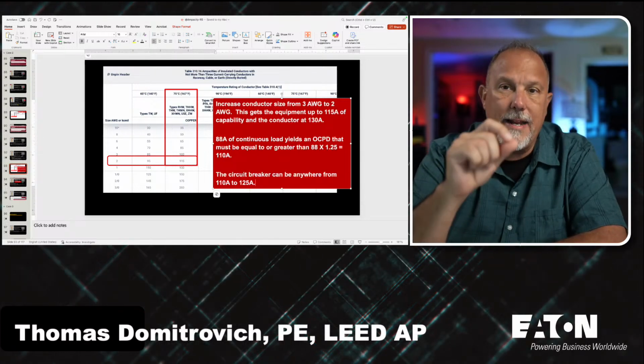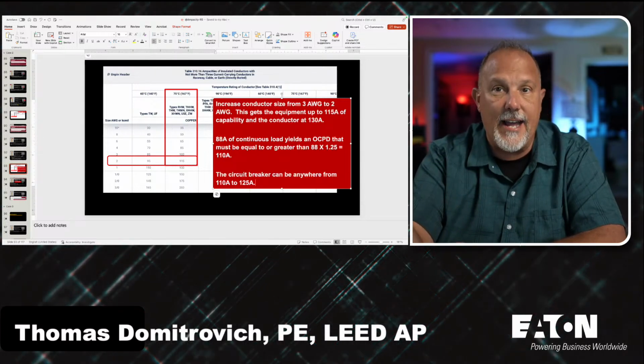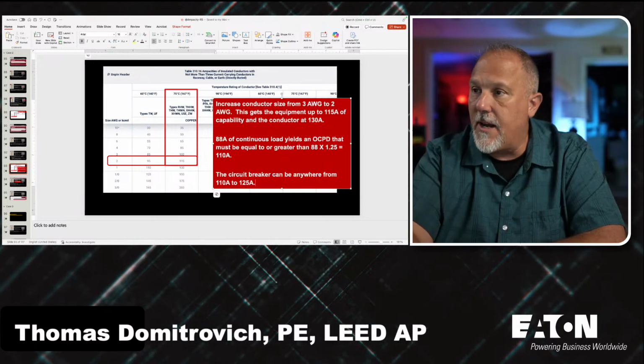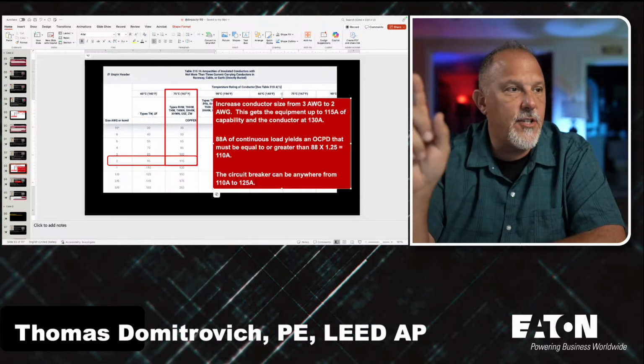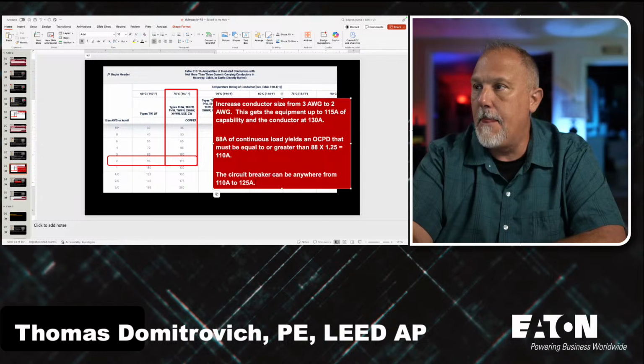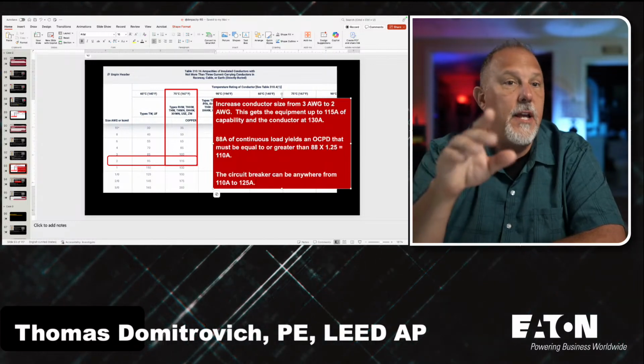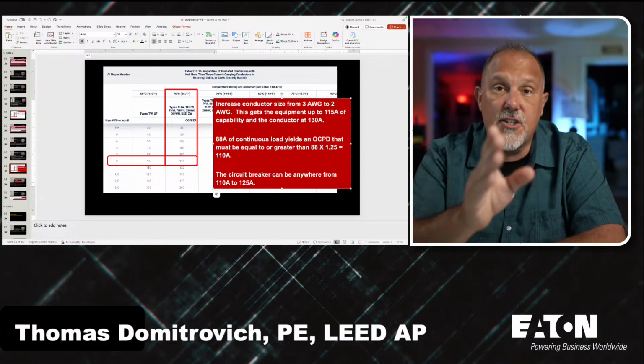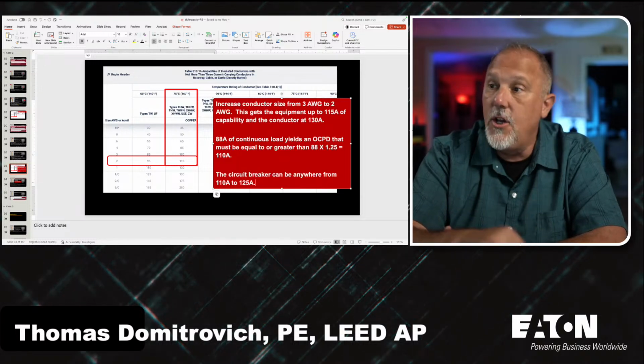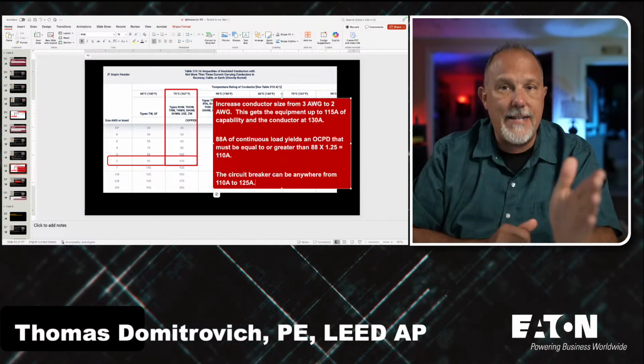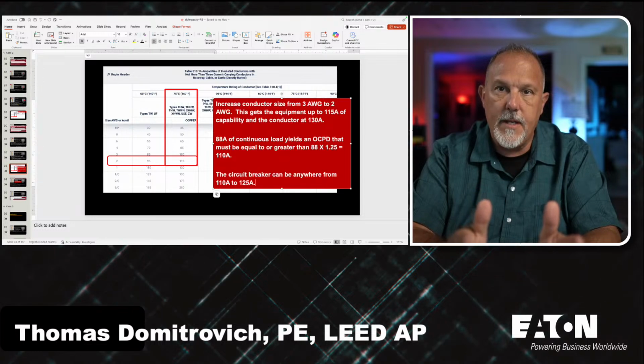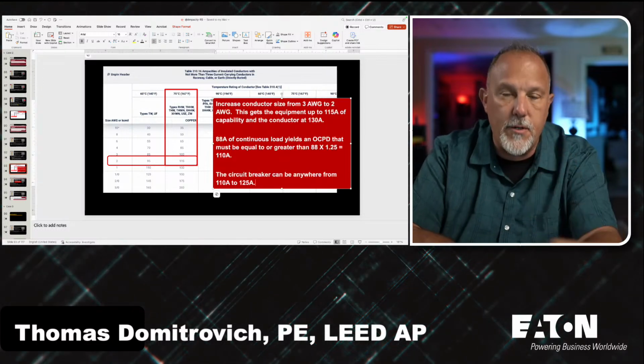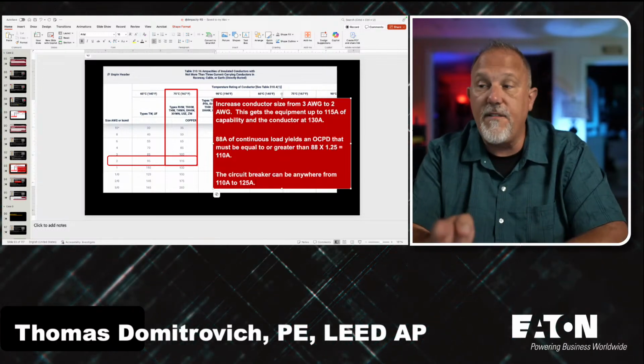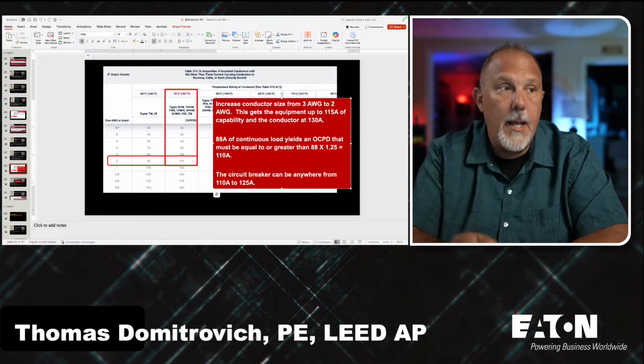Article 240 lets me go to the next higher size. If my circuit ampacity is 115 amps, the next higher size circuit breaker is 125. So I can put anywhere from 110 amp to 125 amp. 110 amp is the minimum because it's 1.25 times 88.